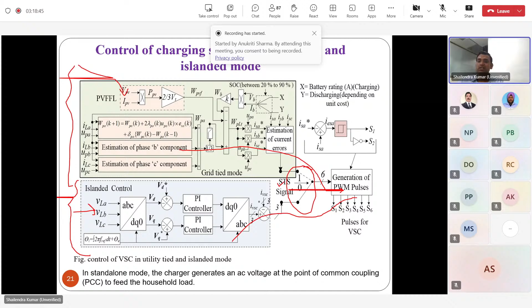So this way, the voltage phase frequency algorithms, islanded control - we have gone through this - and this bidirectional converter control. We take the sensed voltage and compare it with the reference voltage, whatever it should be, like 700, and put it in the PI controller. So we have inner loop and outer loop. The inner loop is responsible to regulate the battery current, and the outer loop is responsible to regulate the DC bus voltage. This way, charging and discharging of the battery is controlled.